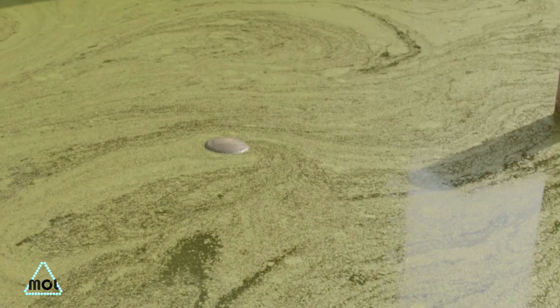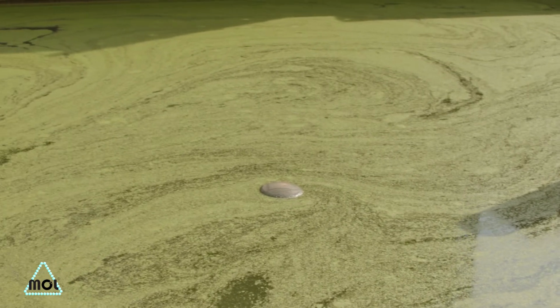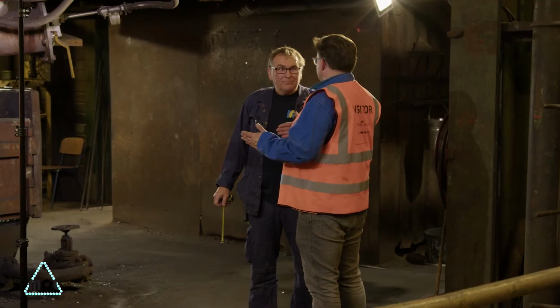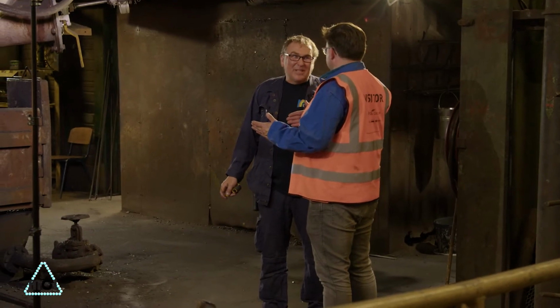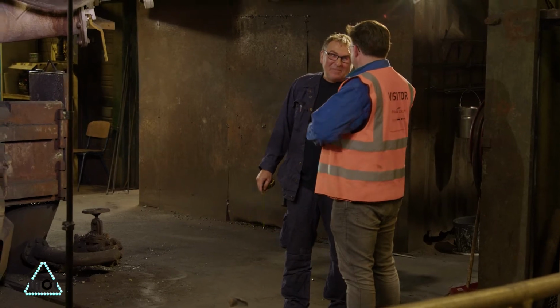The biggest problem that we had was untreated surface water. Untreated water like this gives problems with the cooling systems because we have too much deposit in the heat exchangers and on the surface of the cupola. Here we have the surface of the cupola, and before we only had a big deposit on the surface, about 5 millimeters. It was like a moon landscape.